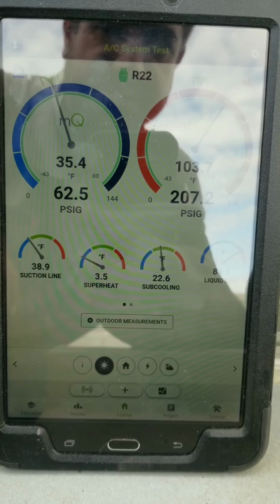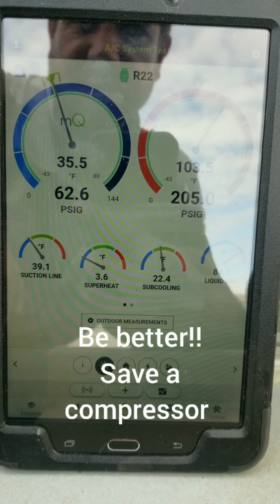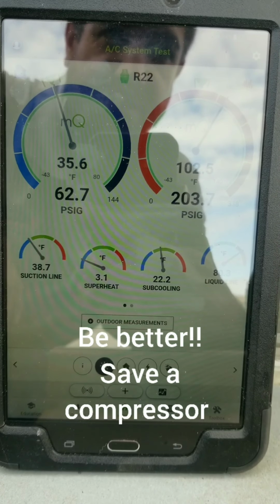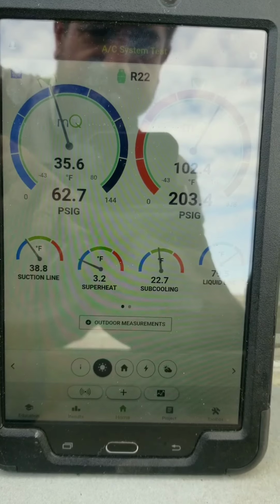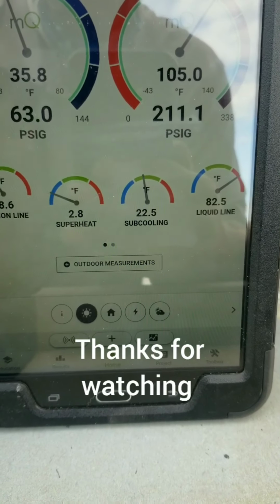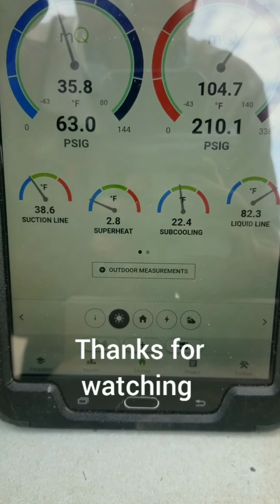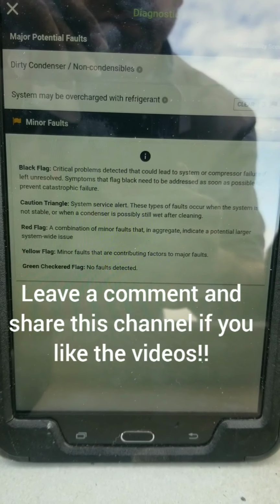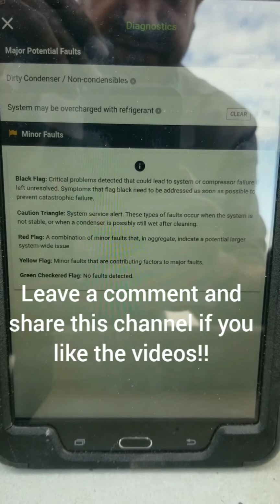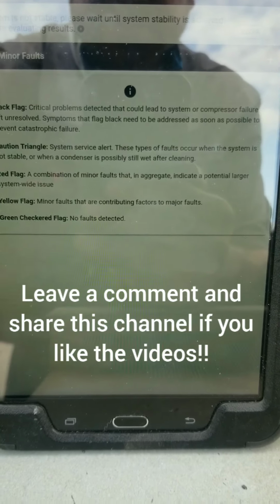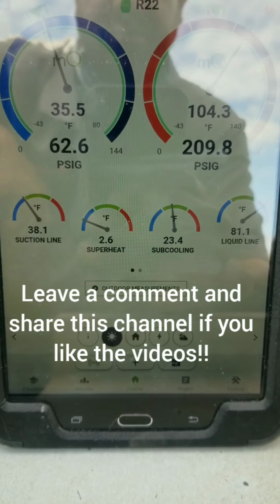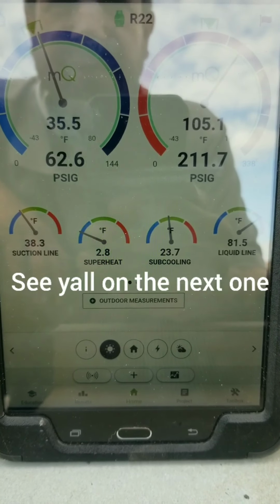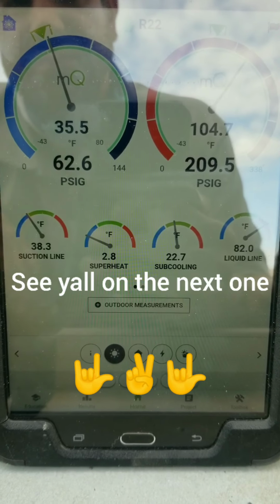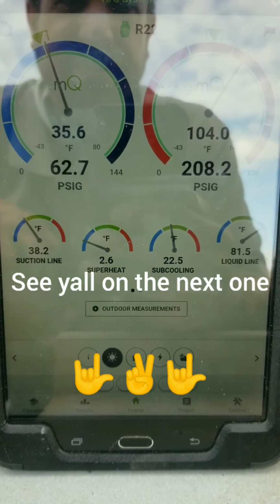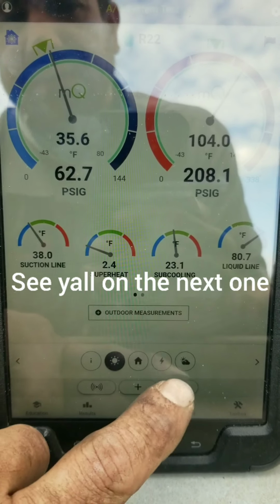We're going to let it run for a few more minutes. We're just going to note everything in our paperwork, let them know what we found, and leave this one be. Hopefully they get another year out of it, and maybe we'll change this unit out next year. Just for shits and giggles here, let's see what Measure Quick says. Measure Quick agrees with me. The condenser's not dirty. I did check that, and it may be overcharged with refrigerant. It's trying to stabilize, but my pressure's going up and down on my discharge pressure. It's undoubtedly been overcharged, but it's going to run for right now. We're going to call this one good.